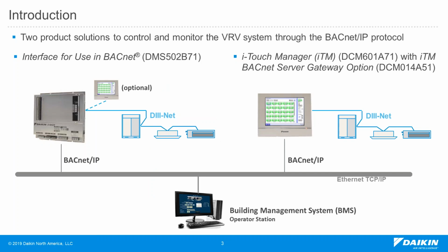So as introduced, Daikin offers two product solutions to the BMS, the Building Management System, to control and monitor the VRV systems through the BACnet IP protocol. The first one is the interface for use in BACnet, the DMS 502B71. It's also known as the BACnet Gateway. It is a hardware gateway that translates Daikin's D3net protocol to BACnet IP protocol so that the VRV system can be controlled by the building management system. It can also work together with Daikin's central controllers, the iTouch Manager.